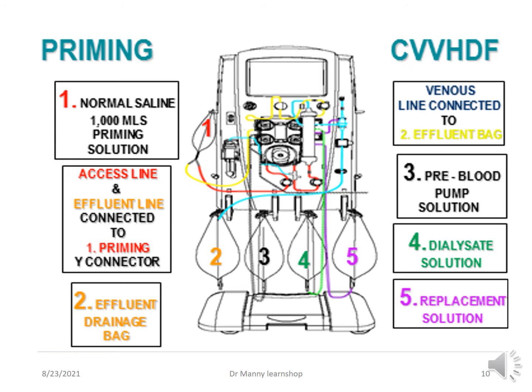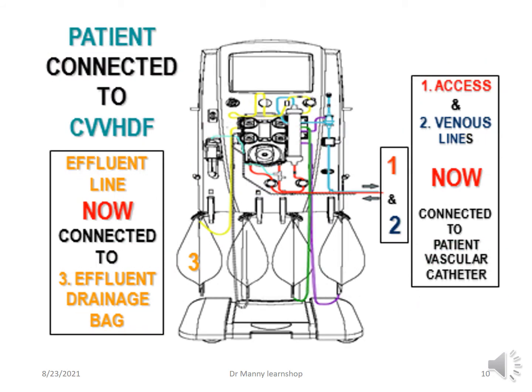You've got the dialysate solution connected, 4, replacement solution connected, 5, pre-blood pump solution connected, also referred to as the substitute. The venous line is connected to the effluent bag, so everything drains into the effluent bag. The access line is doing its job, pulling the priming solution, going through the whole circuit. The venous line is doing its job, returning all the priming solution into the drainage bag. Once the patient's connected to CVVHDF, the effluent line is now connected to the effluent drainage bag, yellow to yellow, and the access and venous lines are now connected to the vascular catheter, which is the patient.